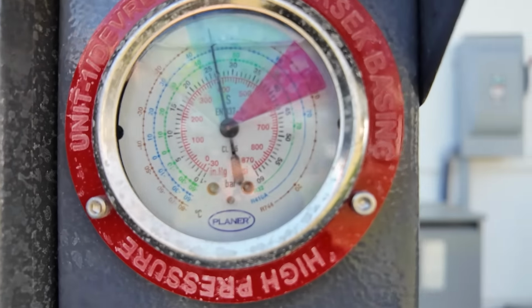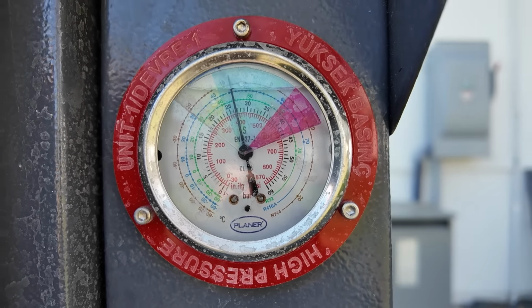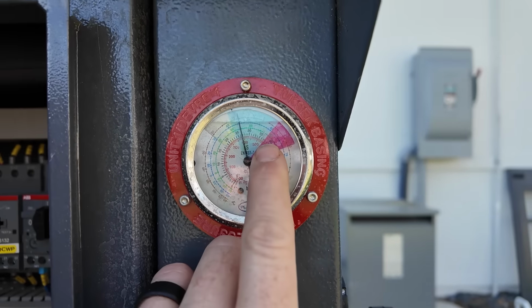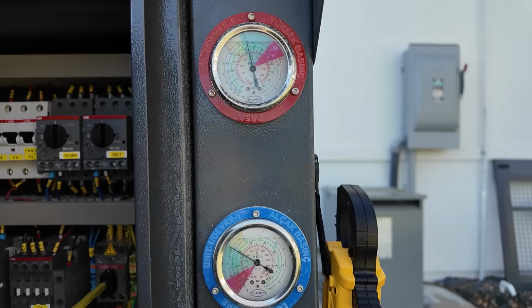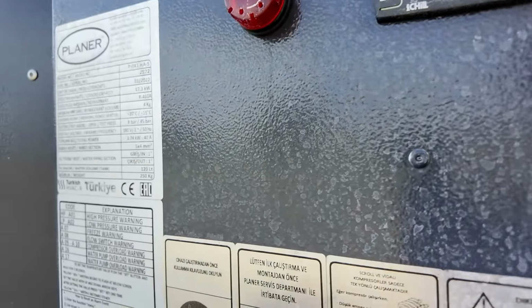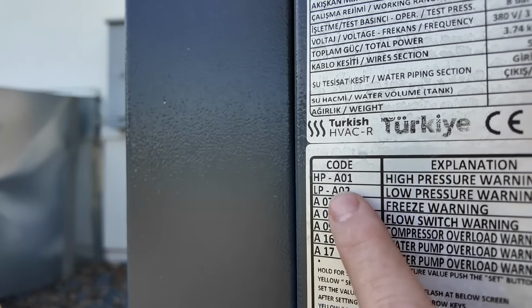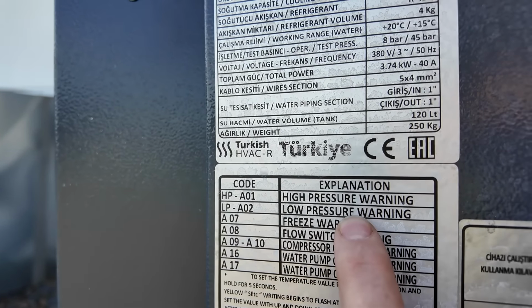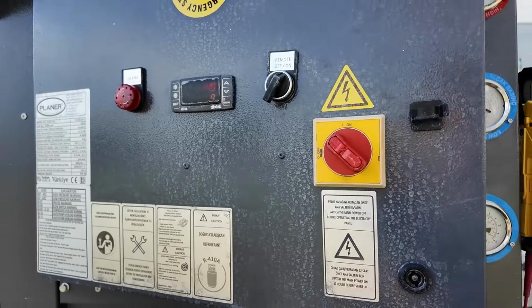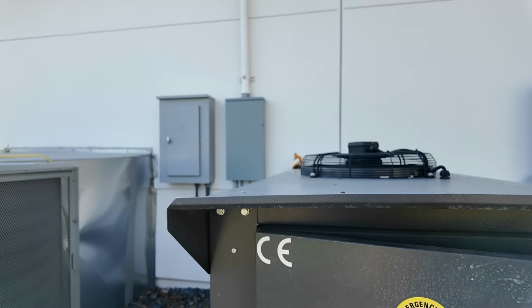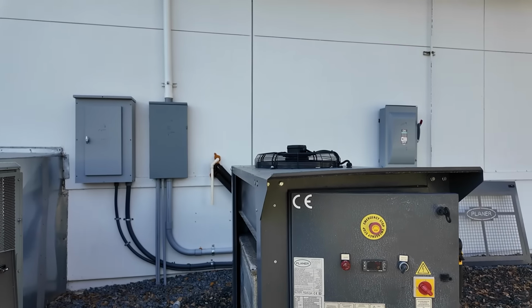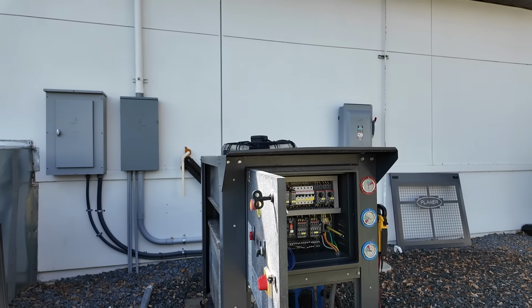have some nice little dial gauges here. Look at that, so fancy. Hit 650 PSI over here in the red range. Tripped off on an alarm. And that alarm actually was A01, saying high pressure, warning. So, like any other service technician, I'm gonna do what's best. And instead of just jumping into it, I'm gonna grab the water hose and clean the outdoor coil.